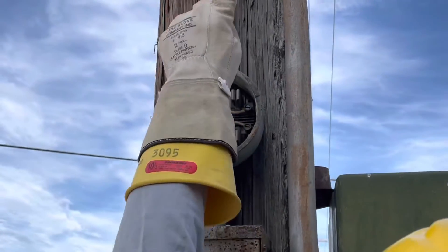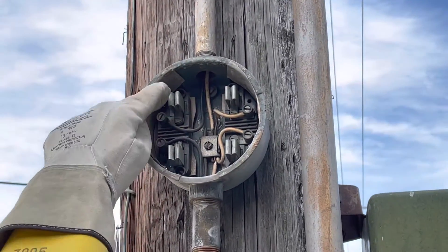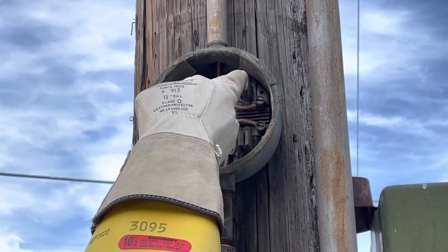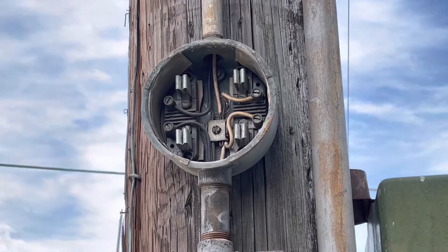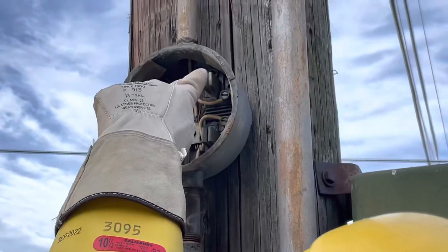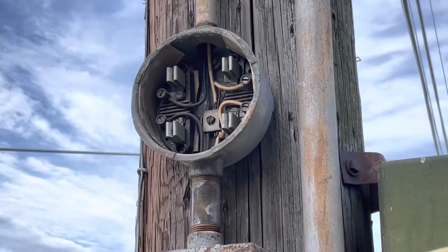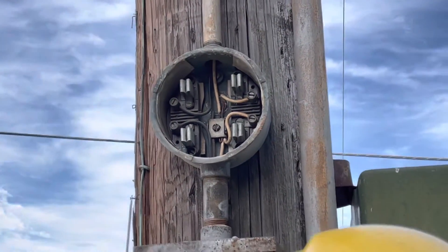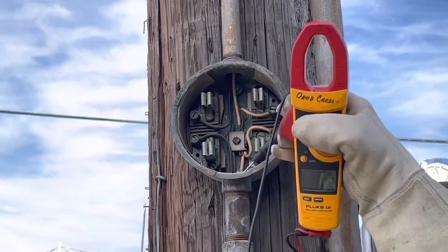I told you it's two wires up there. We have one leg that this one here is 120 volts. This one coming down the pipe is the neutral. You can see the neutral lands here and is jumpered to this lug. So I'm going to check voltage and this is what I should have at this location. I should have 120 volts.